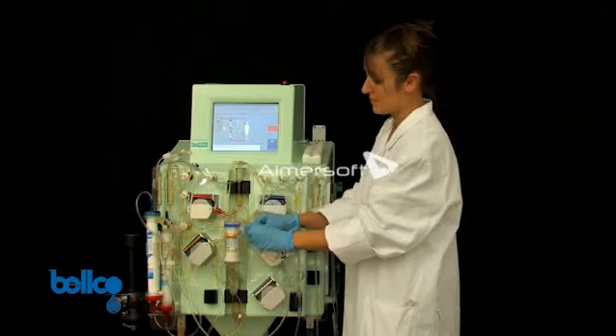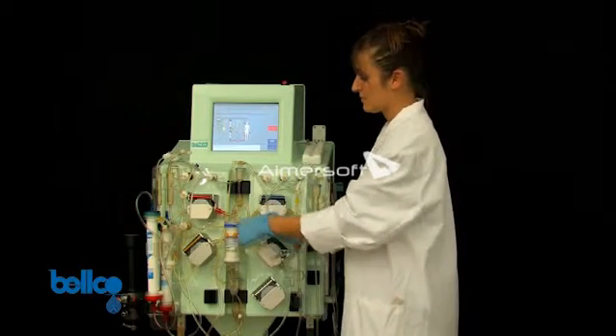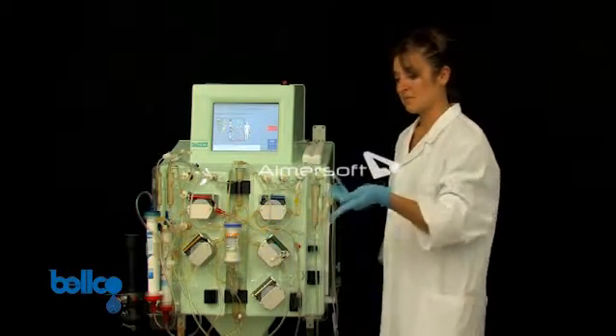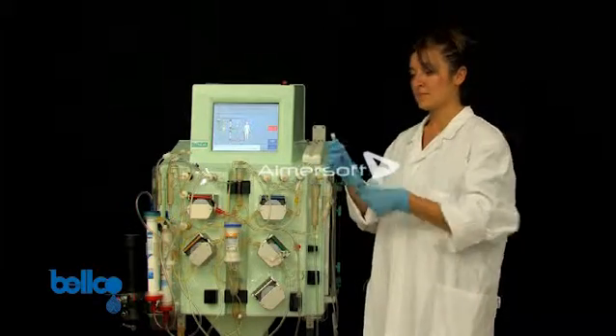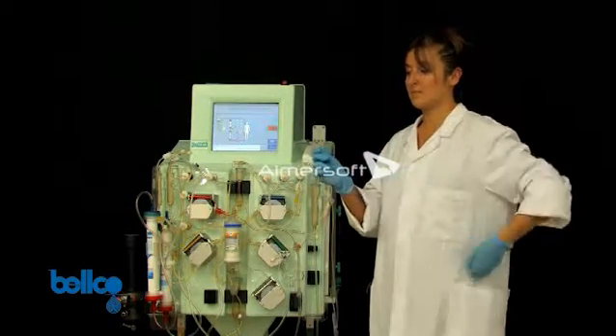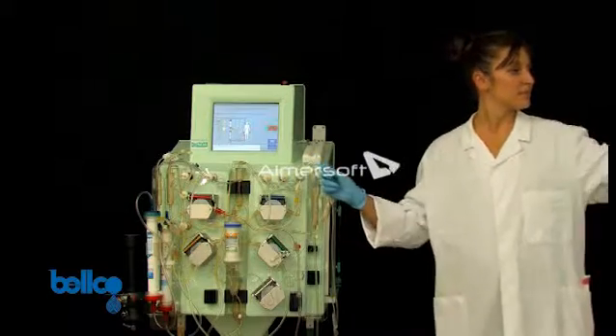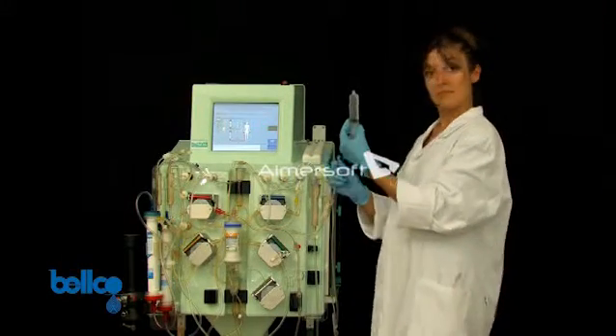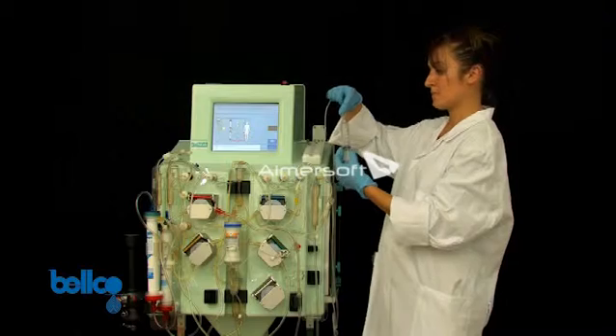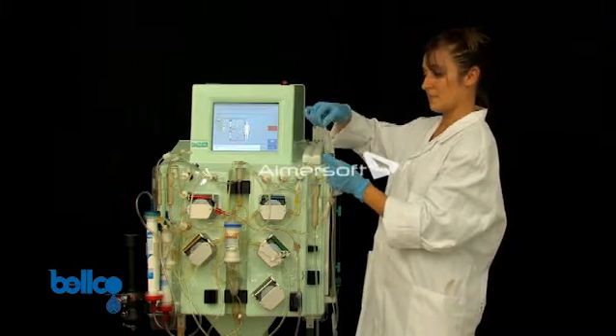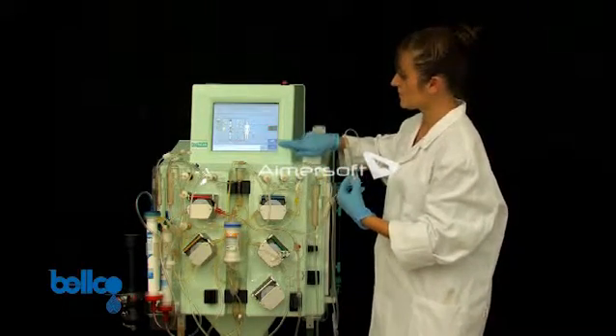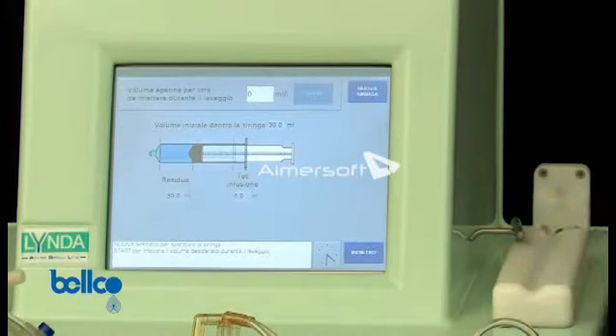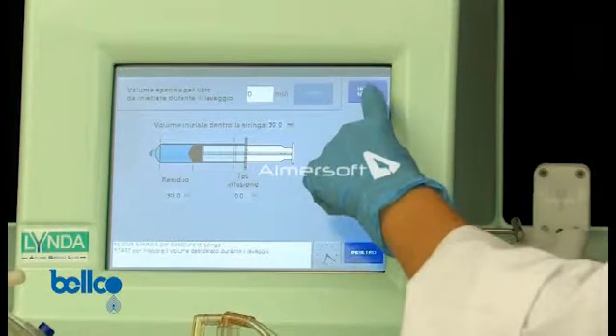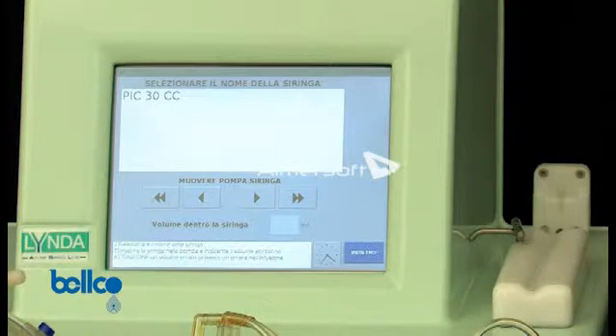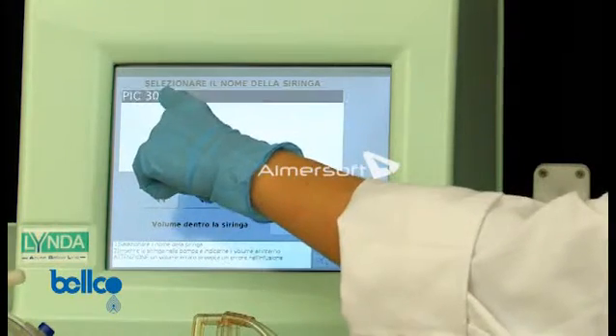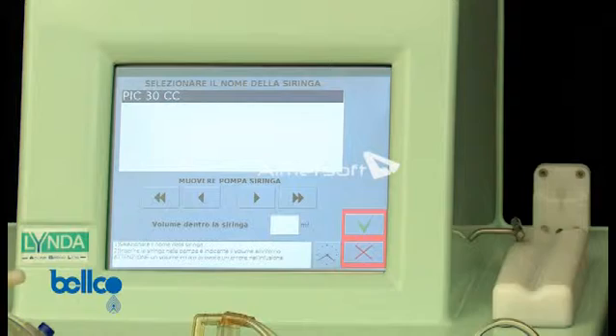To use heparin as anticoagulant, use the syringe pump. Connect the anticoagulation syringe to the dedicated pre-blood pump line. Tap the syringe pump button on the screen and then the new syringe button. Select the syringe type previously set.